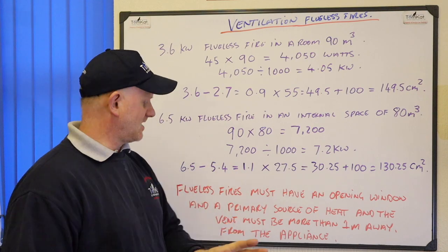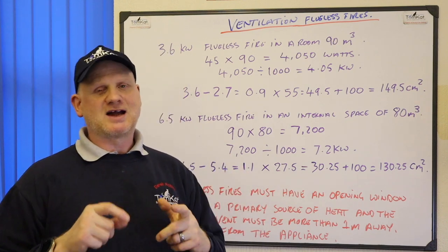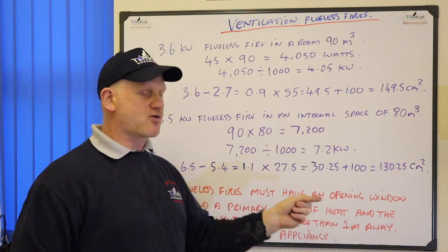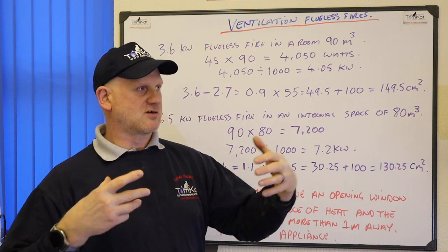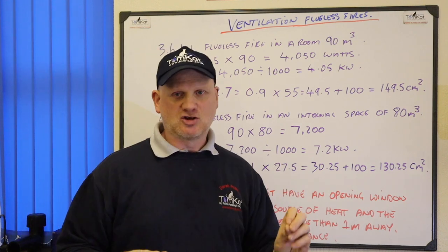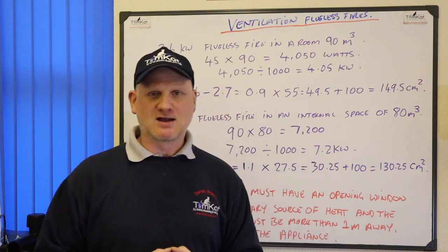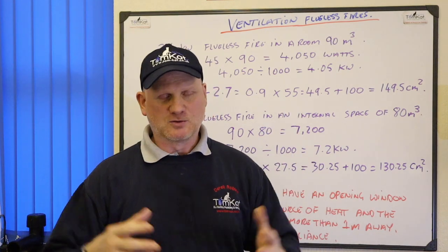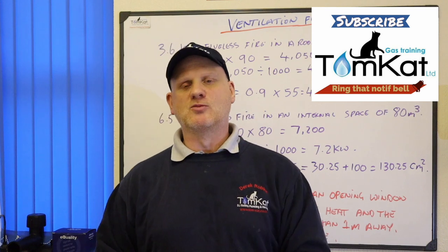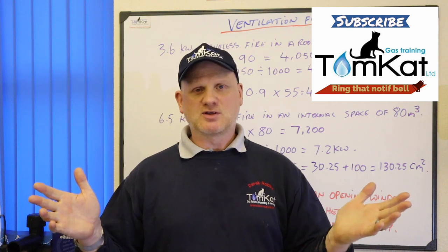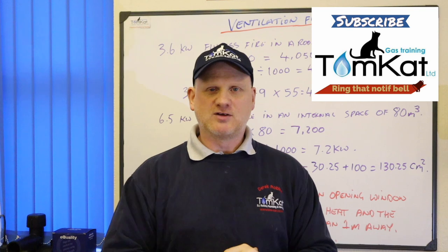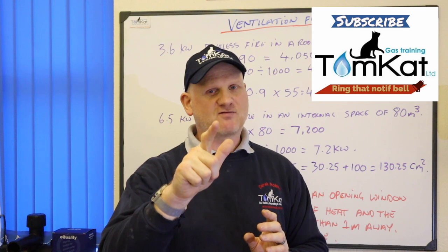Just remember: all flueless appliances require an openable window whether it's a cooker, water heater, or space heater. The flueless space heater also requires a primary source of heat in the room or internal space — so it needs a radiator. The ventilation must be at least one metre away from the appliance to stop the ASD (atmospheric sensing device) or ODS (oxygen depletion system) from vitiating the room. If you liked this video, give it a thumbs up or leave a comment. Subscribe and hit the notification bell — thanks for watching!